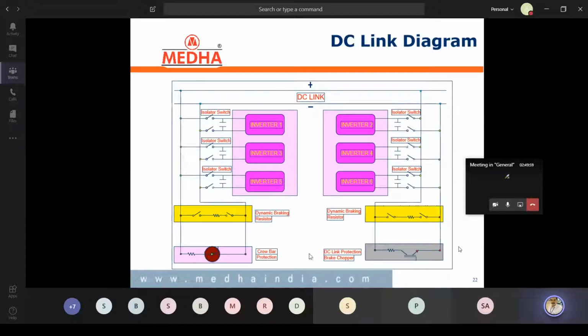But the actual difference between the brake chopper and the crowbar is that the brake chopper is a controlling device. Whenever the DC link voltage is 2800 volts, the brake chopper works in parallel, and the supply goes to the traction motors also. It's a controlling device. But the crowbar fires at 3400 volts by using software, and by using hardware it drives at 3600 volts DC. It's a cut off device. There is no controlling action by the crowbar. The crowbar is a cut off device.